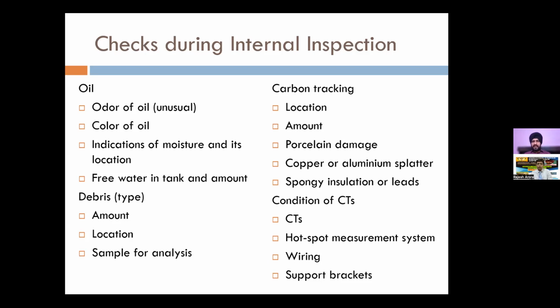Because the first person to enter the transformer is going to be very critical. Once a number of people enter, it is possible that this debris may shift here and there. So it is very important that the first person who enters does a video recording of what he actually finds, so that even if that person is not such an expert, if some expert wants to see it later on, they can verify the actual condition or what could have happened. Then if there is any sign of carbon tracking, you need to identify the location of the tracking, the amount of tracking, and the extent of damage.